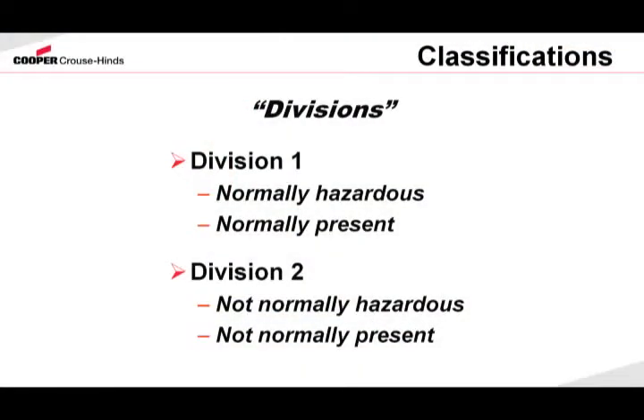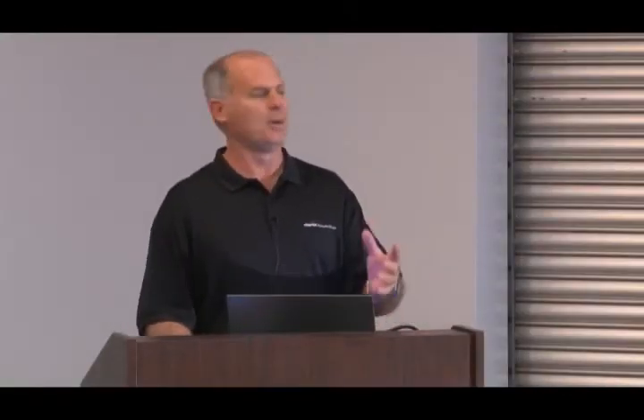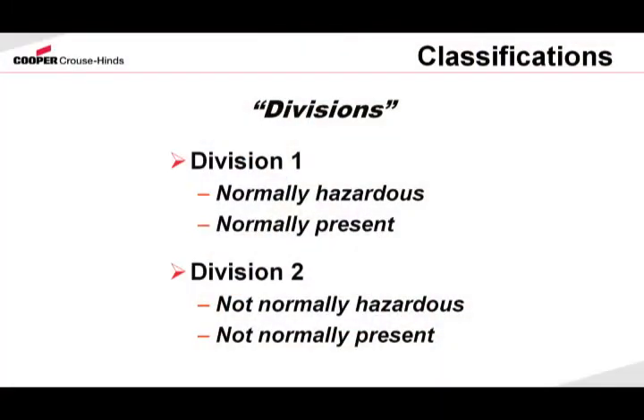We further break down these hazardous locations into divisions. The class was the basic building block. The division tells us whether that flammable gas, vapor, or liquid or combustible dust is present under Division 1 conditions — which means it's normally present — or Division 2, whether it's not normally present. An example: anytime you have a Division 1 boundary around a thief hatch on an oil tank or around a flange on a valve, the area immediately adjacent to that Division 1 area would be automatically classified as Division 2. When we get beyond the Division 2 boundary, we get into non-hazardous locations.